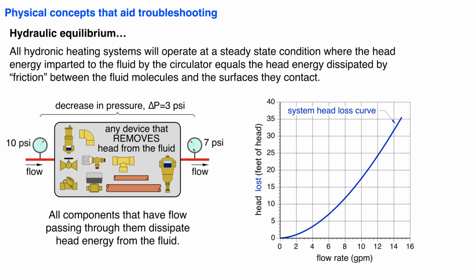So whatever that circuit is, that fluid pathway, as the flow rate through that pathway increases, the head loss goes up. And you can see it's actually a second order curve. It's not a straight line. So the higher the flow rate, the faster the rate that we're dissipating this head energy.